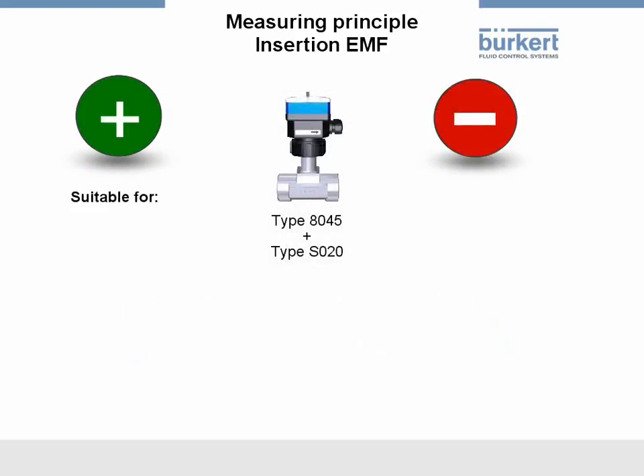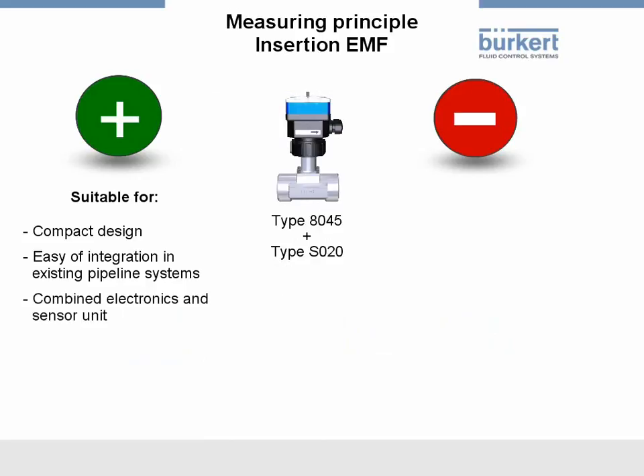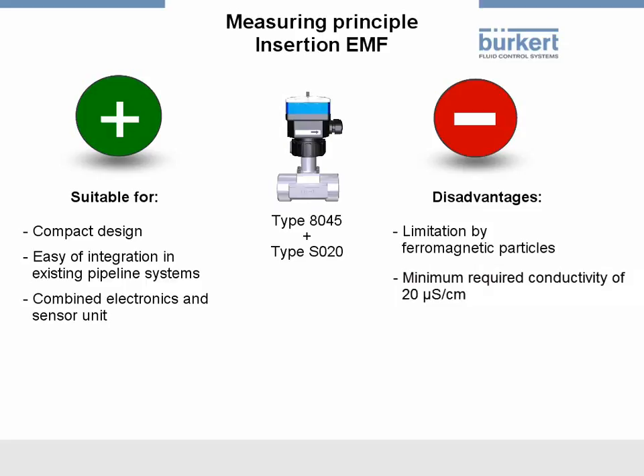The advantages of insertion EMF are the extremely compact design of the device and ease of integration in existing pipeline systems. Another definite advantage for users is that the combined electronics and sensor unit is the same for all diameters, with the exception of one length variant, which makes it very flexible. Disadvantages of this method include the limitation by ferromagnetic particles, the minimum required conductivity of 20 microsiemens per centimeter, and the low measuring accuracy. However, Bürkert insertion EMF allow on-site calibration for adaptation to the respective application and so increase the accuracy.